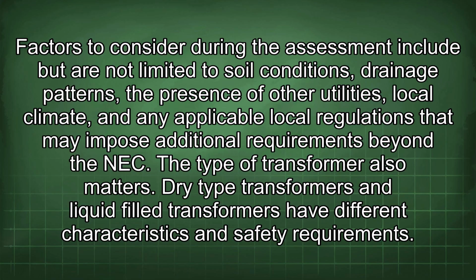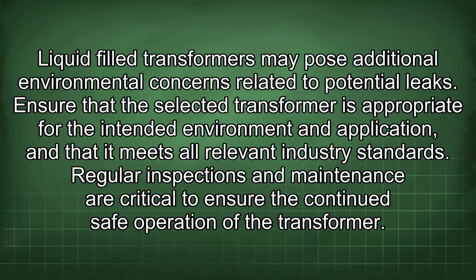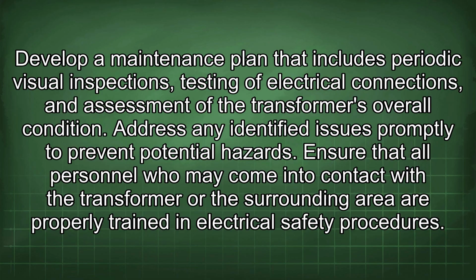The type of transformer also matters. Dry-type transformers and liquid-filled transformers have different characteristics and safety requirements. Liquid-filled transformers may pose additional environmental concerns related to potential leaks. Ensure that the selected transformer is appropriate for the intended environment and application, and that it meets all relevant industry standards. Regular inspections and maintenance are critical to ensure the continued safe operation of the transformer. Develop a maintenance plan that includes periodic visual inspections, testing of electrical connections, and assessment of the transformer's overall condition. Address any identified issues promptly to prevent potential hazards.